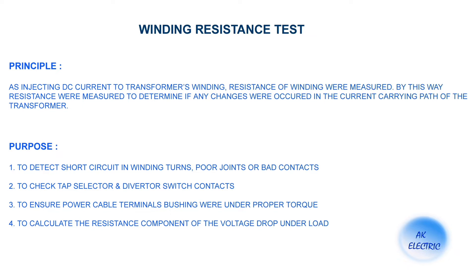Purpose: to detect short circuit in winding turns, poor joints or bad contacts, to check tap selector and diverter switch contacts, to ensure power cable terminals bushing is under proper torque, and to calculate the resistance component of the voltage drop under load.